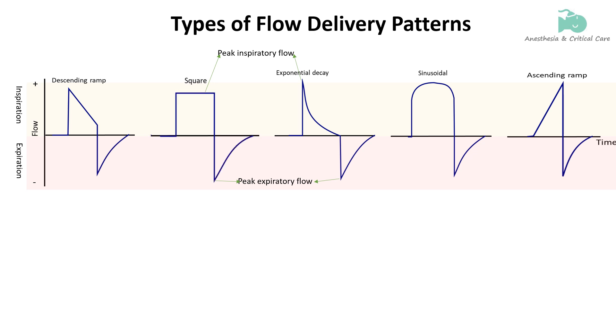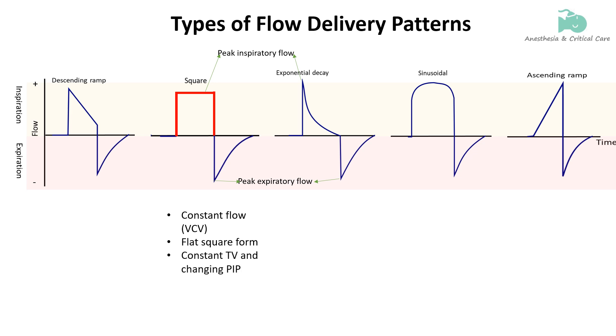The square flow waveform is characteristic of volume-controlled ventilation, where the ventilator delivers a preset volume of air at a consistent, unchanging rate throughout the inspiratory phase. This constant flow rate is represented by a flat, horizontal line on the flow-time waveform. At the end of inspiration, the flow rate suddenly drops to zero, shown by a sharp vertical drop, marking the transition from inspiratory to expiratory phase. This consistent flow ensures the full tidal volume is delivered, but can increase peak airway pressures, especially in patients with stiff lungs.